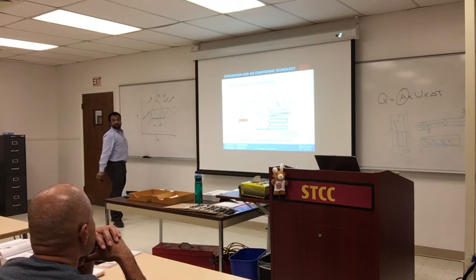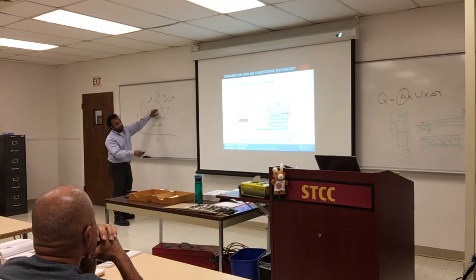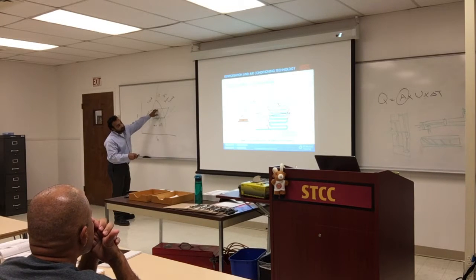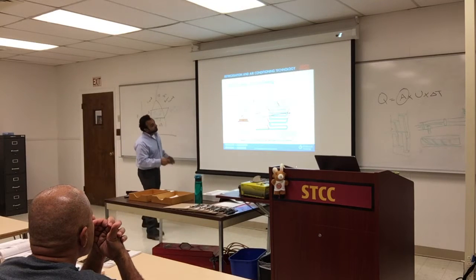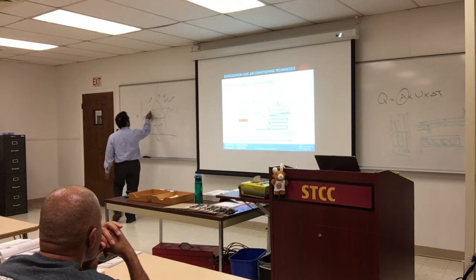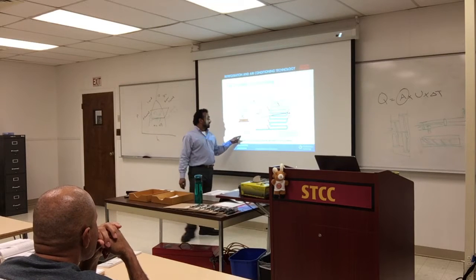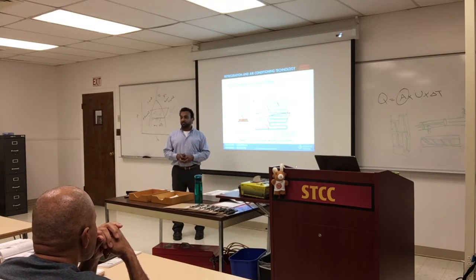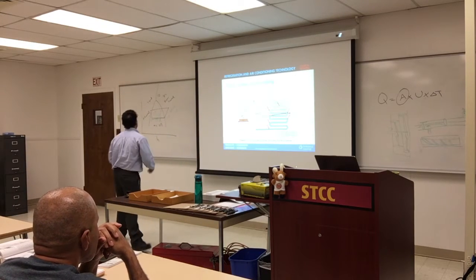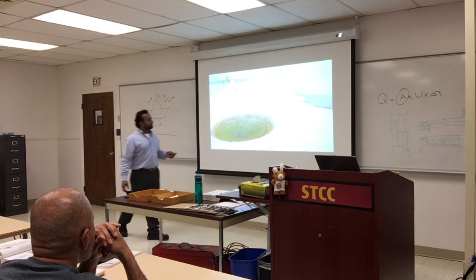It's going to be some cool liquid, but it's high pressure. So we keep the pressure constant. Look at the gauges. Here the gauge is 278, and it's supposed to be the same over here. There is a gauge that says the same thing. The pressure does not change, but the temperature is decreasing. So we went below the line here. We went to subcooled completely, and so you're going to get some cooled liquid to the expansion valve. What the expansion valve does is give it a lot of space and release the pressure. You release the pressure, and you're going to get a lot of heat absorbed.